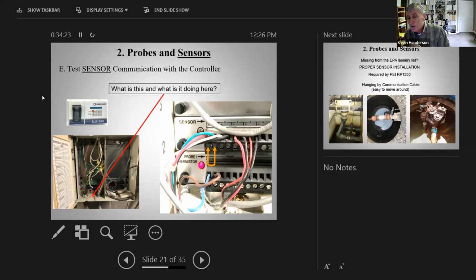If you short that, jump across there with that little wire right there, then it will go into alarm. And so the reason I bring this up again is there really is no reason for anybody to ever do this, except when you have a double-walled fiberglass tank and the guy cannot get the sensor out. He may be tempted to just go into the console, find which one of these little 2-wire sets goes to the tank interstitial and jump across it and cause an alarm. And it will go into the alarm history. It will appear that he pulled the sensor and did the actual functionality test. And in fact, all he really did was jump across the positive and negative and cause it to go into alarm. So you just need to be aware of that. Hopefully that never happens to anybody, but lots of people know that trick.